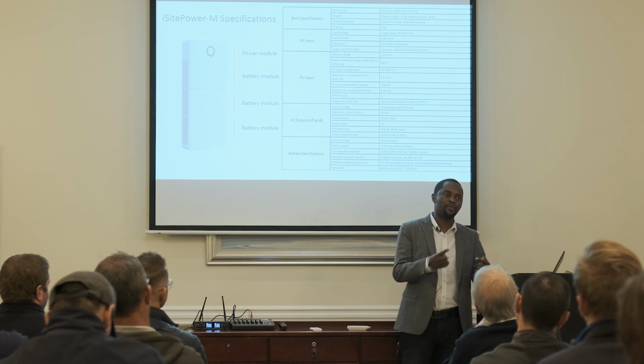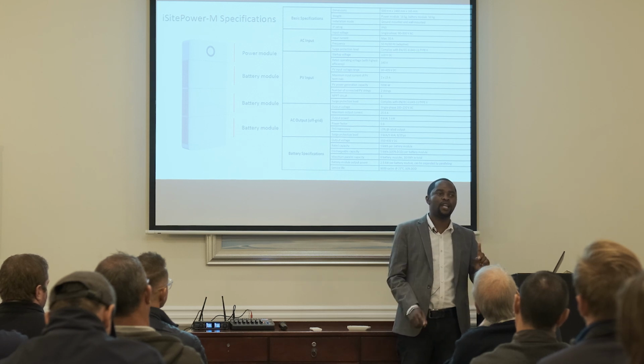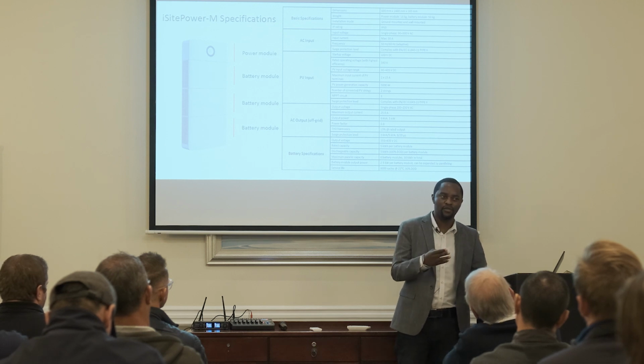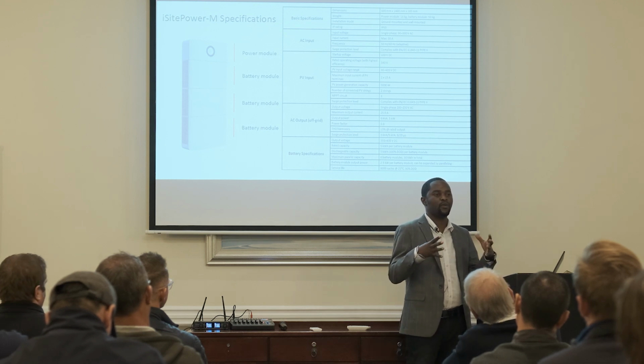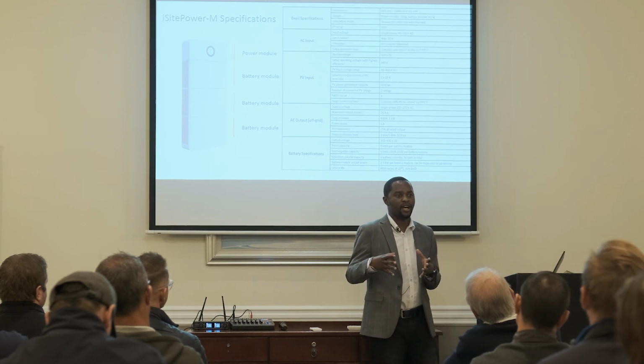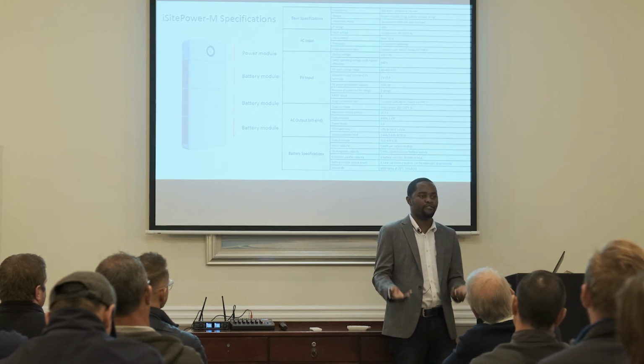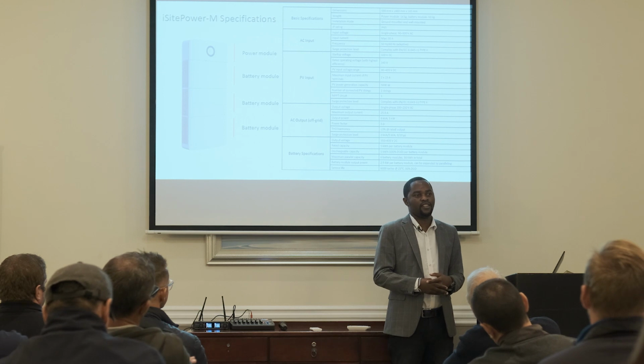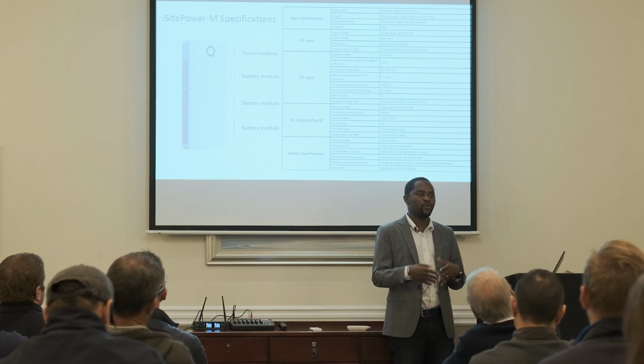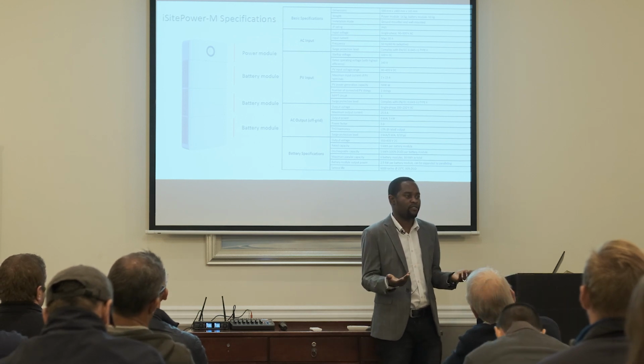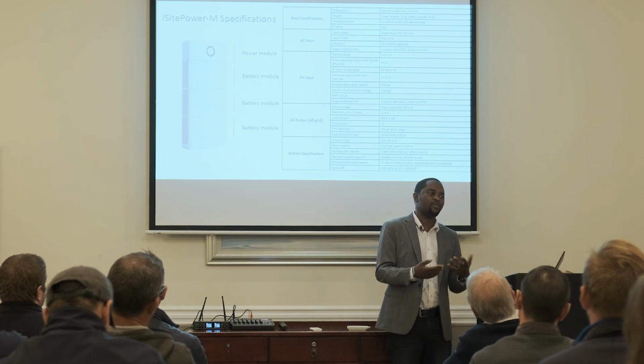What it means, if you've got one battery and you are charging at maximum, you need an hour from 0 to 100%. If you've got 2, you need 2 hours. If you've got 3, you need 3 hours, because the inverter can only charge at 5 kilowatt per hour, since it's also a 5 kilowatt inverter. Right? Then if you've got one battery, you might not need to charge it at 1C, you can charge it at 0.5C.